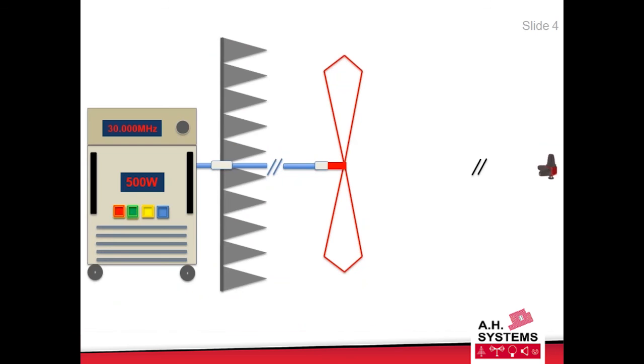Here we have a test setup, and it looks very simple, but holds a lot more information than you might at first think. First of all, observe there's a horizontal line going from the bulkhead connector of the chamber, along in a straight line through the antenna feed cable to the antenna, and then the two little diagonal lines, of both the blue and the black set, mean the distance is not as shown. And then we have a field probe, and note where the field probe is. It's on that horizontal line.